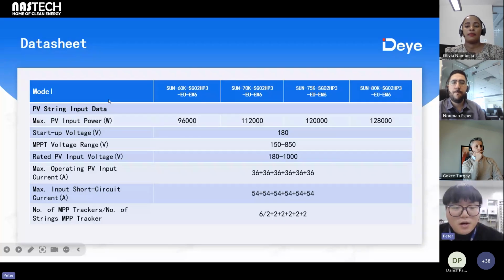And the PV input power is usually more than 1.5 times the rated power that you can input. When you input the PV power into the inverter, it can convert 60K of the power to AC output, and the rest, if there is exceeding, it can charge your battery from DC to DC, so it will not cause any energy waste unless your battery is already full. And the PV start voltage is 180. And we can connect panels within 180 to 1000 volts.